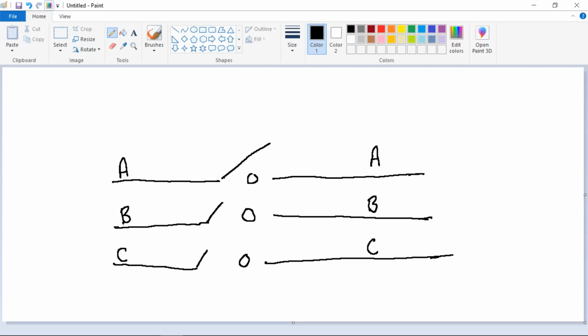What would happen if I close this switch, erase that, and change this to B, and change that to A. And the configuration of feeder circuits as far as the phasing is concerned can change because I need to turn corners. I need to go underground. Whatever I need to do on the entirety of the circuit may change the phase location in multiple instances. So this can happen regularly.